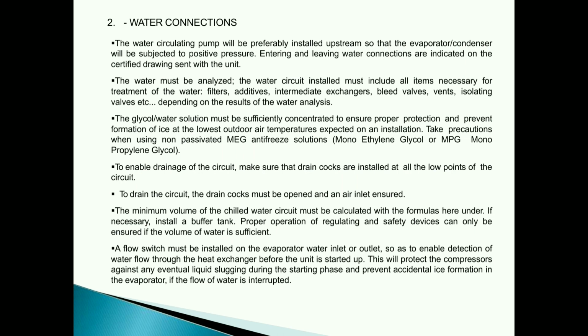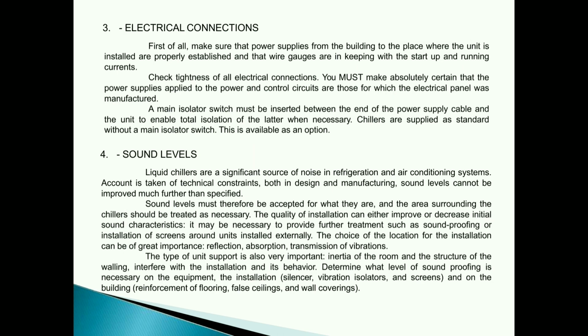The minimum volume of the chilled water circuit must be calculated with the formulas hereunder. If necessary, install a buffer tank. Proper operation of regulating and safety devices can only be ensured if the volume of water is sufficient. A flow switch must be installed on the evaporator water inlet or outlet, so as to enable detection of water flow through the heat exchanger before the unit is started up. This will protect the compressors against any eventual liquid slugging during the starting phase and prevent accidental ice formation in the evaporator if the flow of water is interrupted.